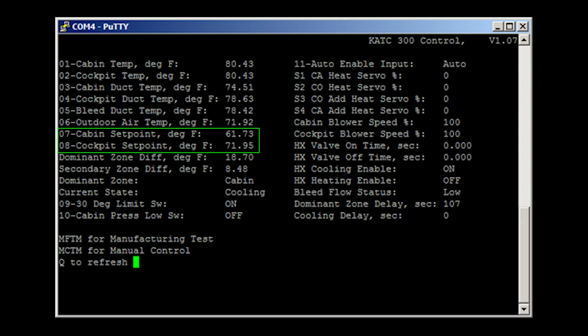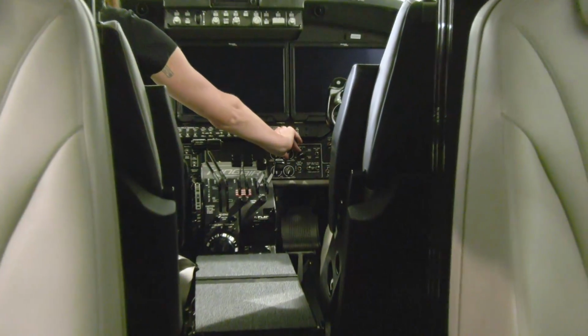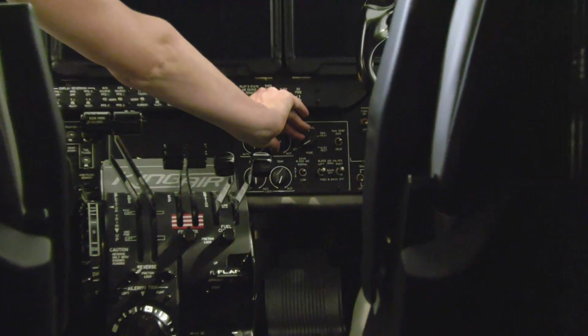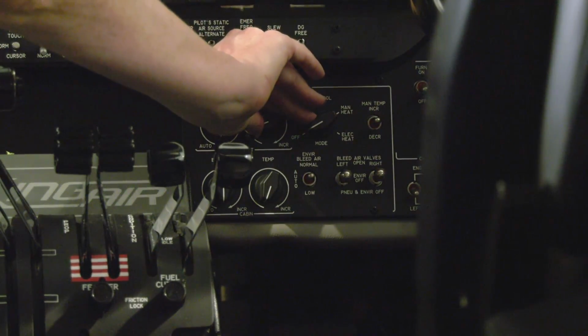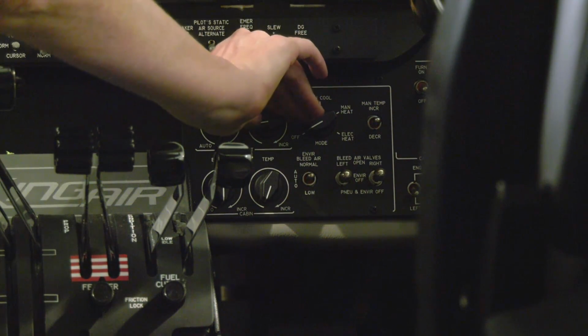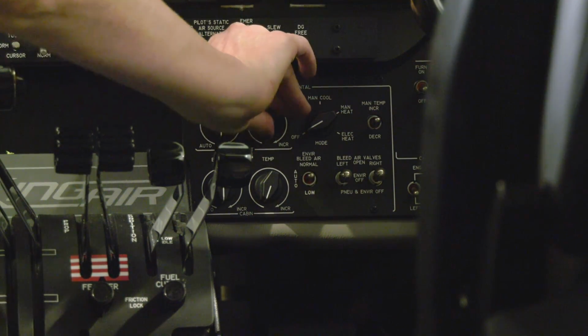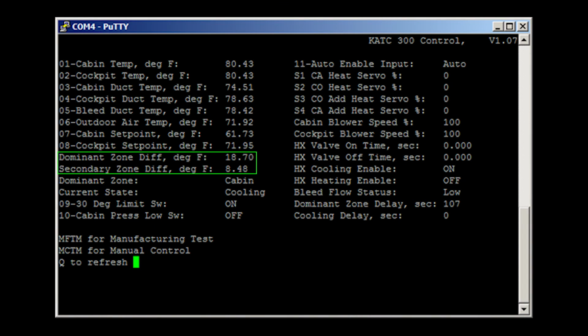The next values are for the set points. These are measured by potentiometers located on the co-pilot subpanel. The values will be between 60 and 90 degrees Fahrenheit. You should be able to watch these values change on the diagnostics screen while turning the knobs. The zone differences are the difference between the headliner sensors and that set point value. The larger value, either cockpit or cabin, is the dominant zone. The controller's heating or cooling logic will drive to reduce the differential amount of the dominant zone.